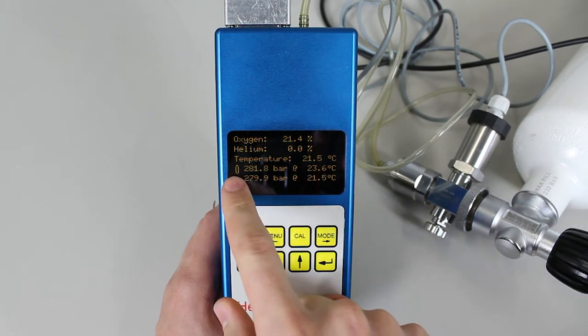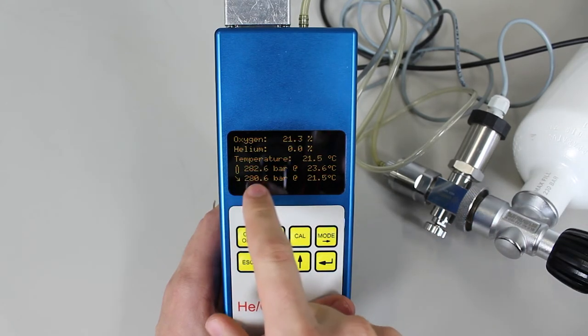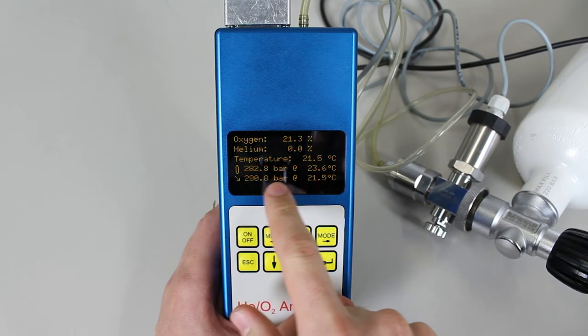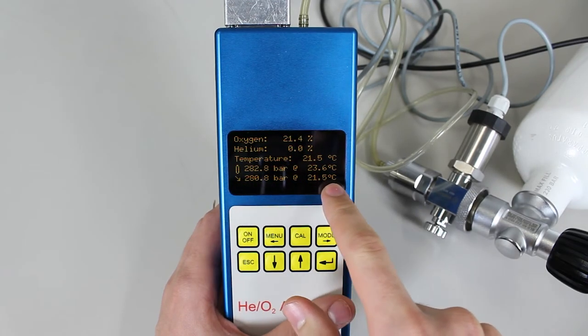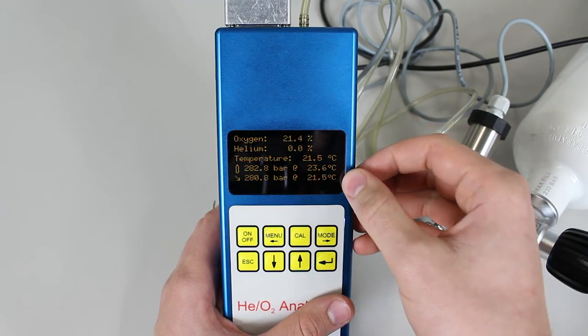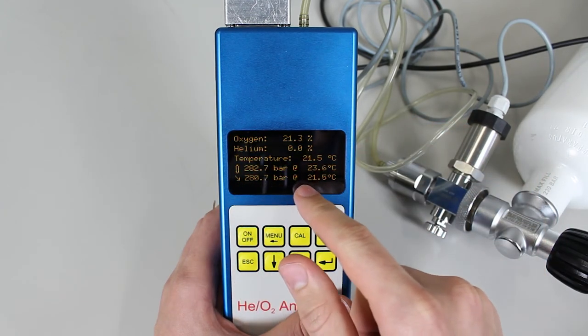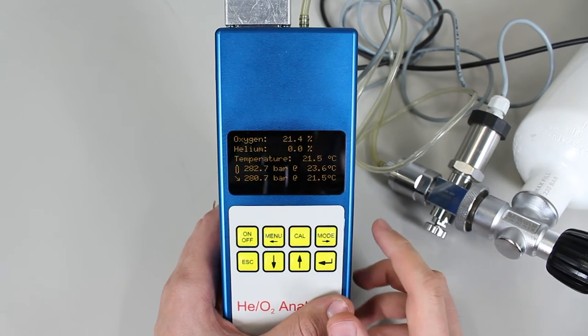we can see the immediate pressure of the tank right now and the pressure which the tank will have when it cools down to the set room temperature. Right now it's 23.6 and this is the pressure it will have when it reaches 21.5 degrees Celsius.